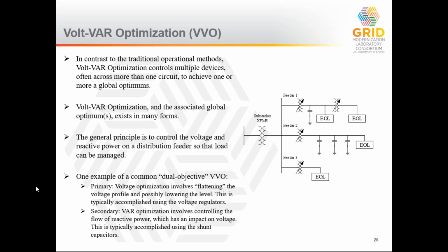On the right-hand side I'm showing a very simple example of a substation transformer with 3 distribution circuits coordinating the operation of 4 voltage regulators and 4 shunt capacitors, and it has some end-of-line measurements. These are meters out there that can measure the point so they can determine how low the voltage should be.